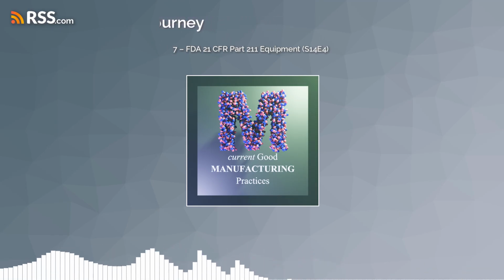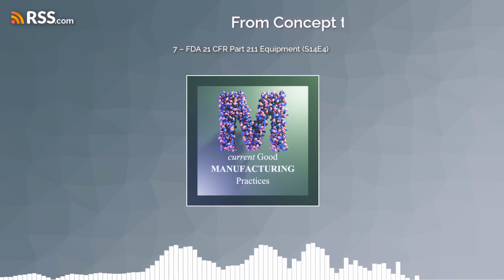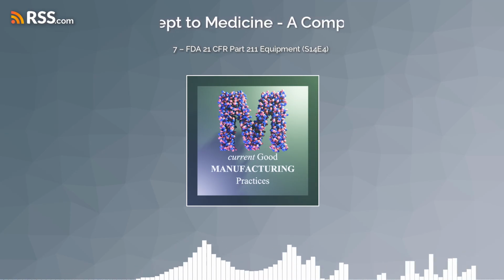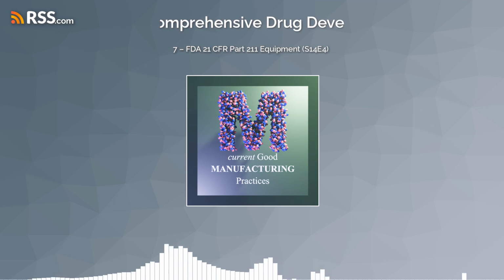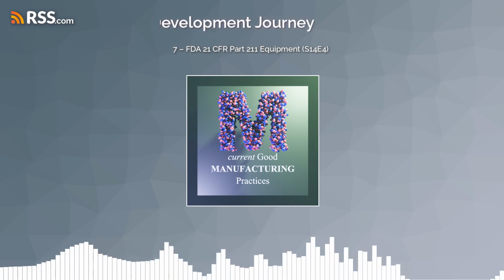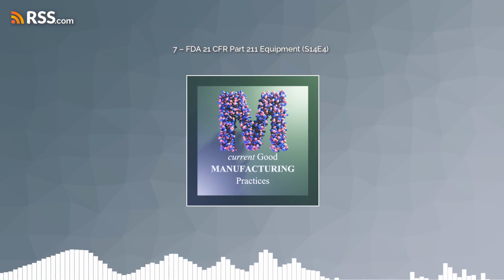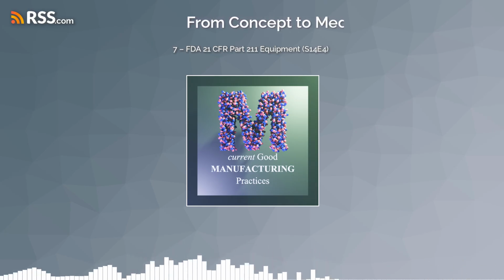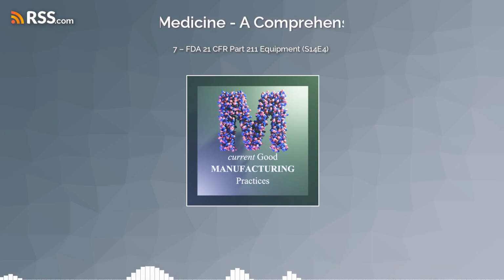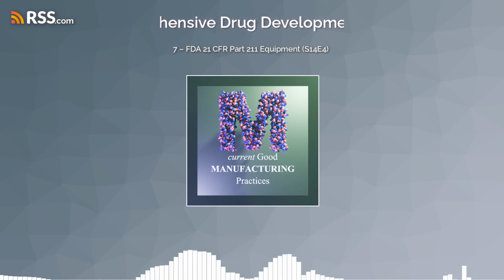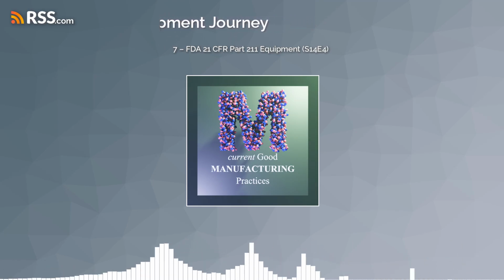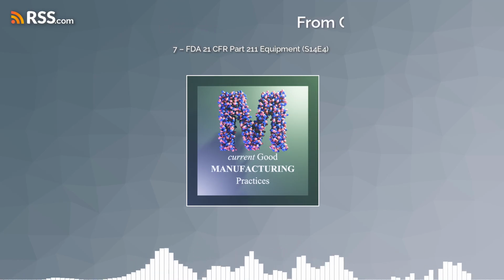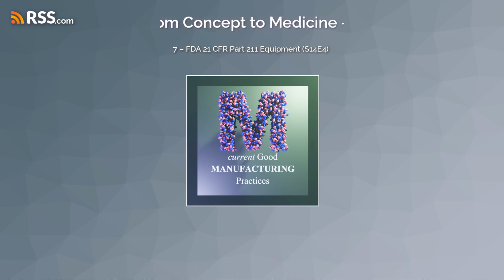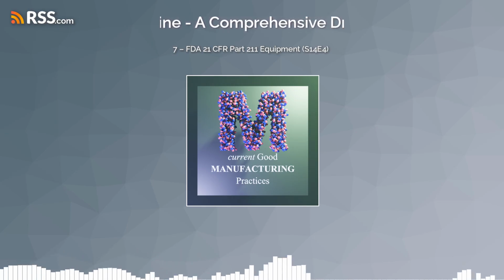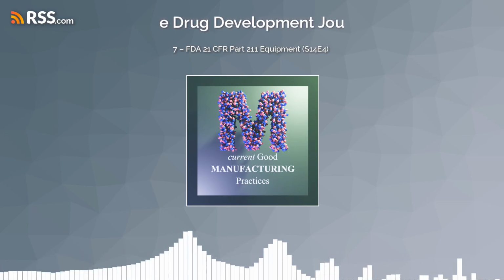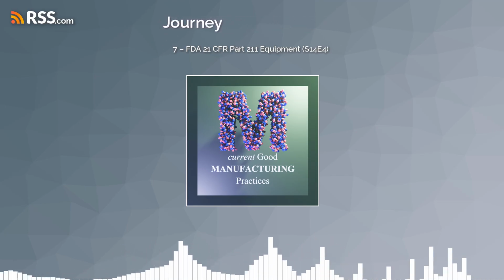Could you give me an example of how CAPA might be used to address an equipment issue? Sure, let's go back to that example of the improperly calibrated equipment. The investigation might have revealed that the calibration procedure was outdated or that the technician who did the calibration wasn't trained properly. So those are the root causes, the underlying reasons for the problem. Yeah. How would CAPA address those? Well, the company might make some changes to the way things are done, like updating the calibration procedure to reflect the current best practices. They might provide additional training to the technicians. To prevent similar problems in the future, they might also put in place a system to review and update those procedures regularly, or implement a more robust training program for all personnel who work with the equipment. So it's about learning from the past and taking concrete steps to avoid making the same mistakes. Exactly. It's that commitment to continuous improvement, driven by thorough investigations and effective CAPA, that helps ensure pharmaceutical manufacturing processes are reliable and safe.